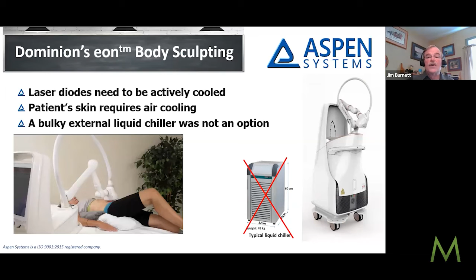So we made a very small pair of refrigeration systems for this unit that are now embedded, using a direct refrigerant approach with no reservoir and no pump. We made room for two of these units, one cools the laser diodes, and the other cools the air that passes over a heat exchanger on the cold plate, running down the tube along with the fiber laser to the treatment point. This is another example of how we integrate these small systems to enable a much smaller unit for the treatment room.